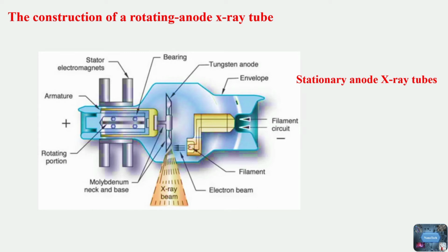The electrons interact with the material of the anode, slow down and stop. Most of the energy absorbed from the electrons appears in the form of heat, but a small amount appears in the form of X-rays. Some of these X-rays pass through the exit window of the insert and housing and through the patient to form the X-ray image. X-rays that are emitted in other directions are absorbed by the housing. The complete tube assembly is mounted on a support and provided with a collimator.